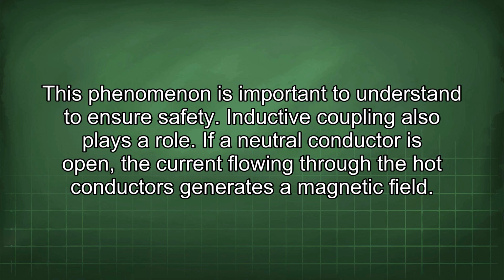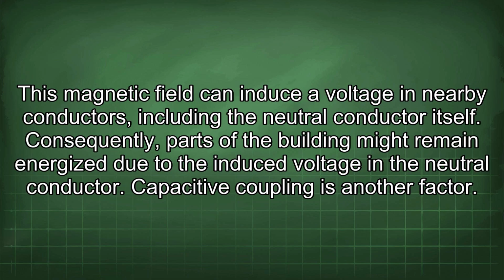Inductive coupling also plays a role. If a neutral conductor is open, the current flowing through the hot conductors generates a magnetic field. This magnetic field can induce a voltage in nearby conductors, including the neutral conductor itself. Consequently, parts of the building might remain energized due to the induced voltage in the neutral conductor.